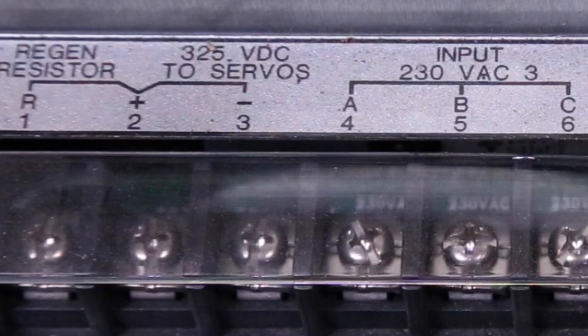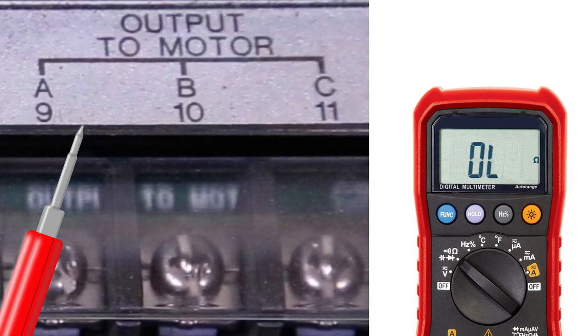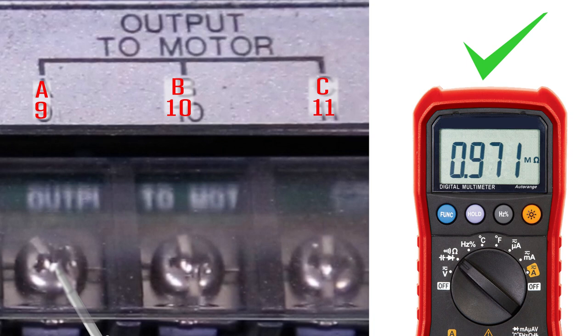First, check the output on the positive side of the DC bus. Set your multimeter to resistance test mode and put the black lead onto terminal 2. It's labeled with a plus sign. Use the red lead to measure the resistance to motor terminals 9, 10, and 11. These are labeled A, B, and C.